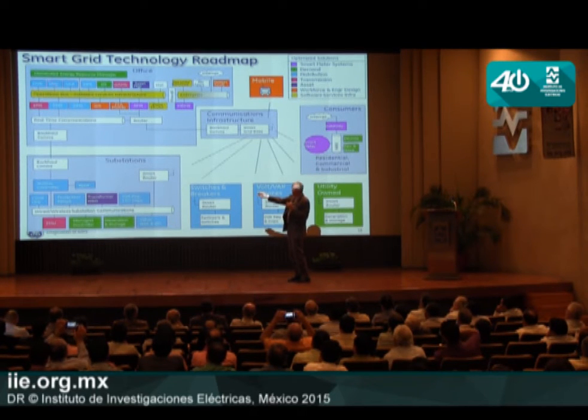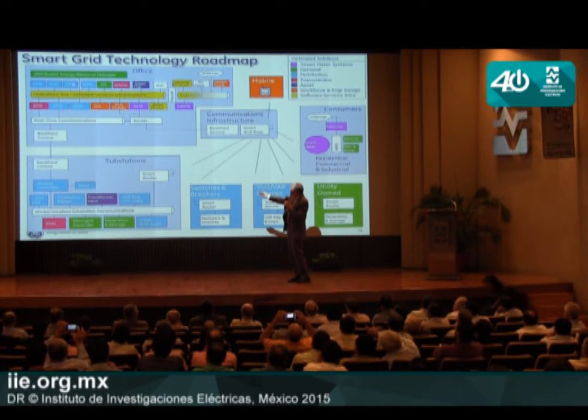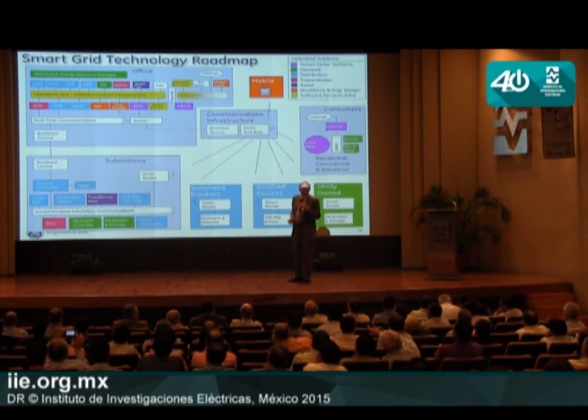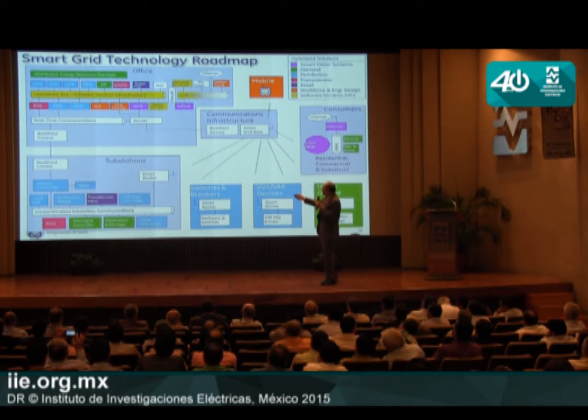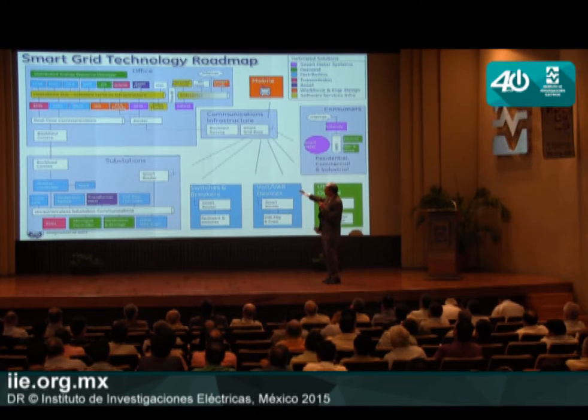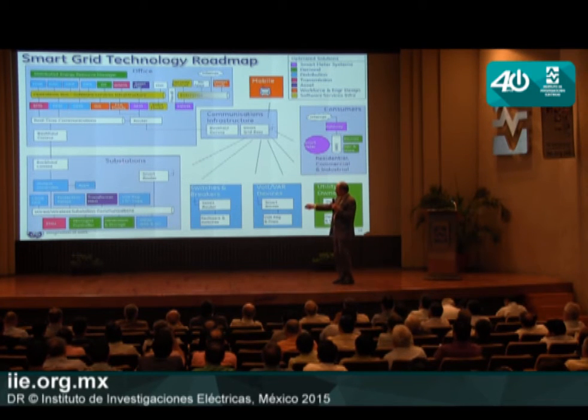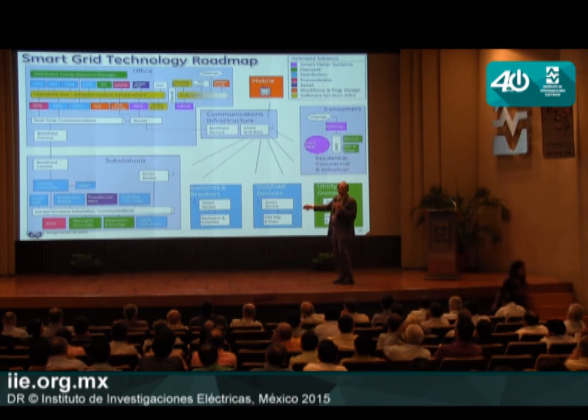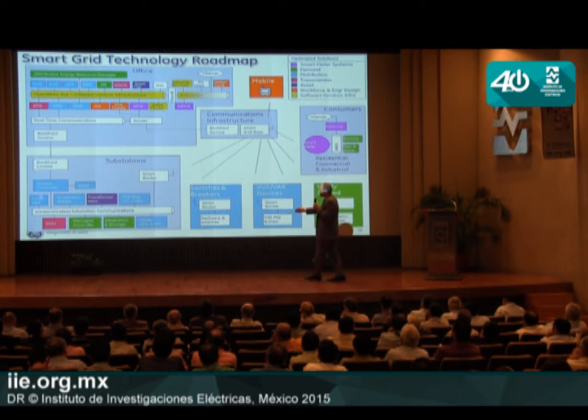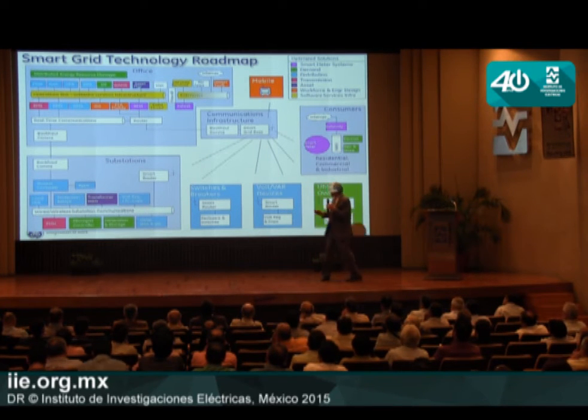So there's fault detection, isolation, restoration, integrated volt-var control, optimal feeder reconfiguration, distribution power analysis. That's our 3-phase unbalanced load flow here. These are the systems, distribution management, outage management, and these are located in the office or the control center, all right? Now we go down to the substation, and here we have our data concentrator, our station controller. And like I said, we're distributing the intelligence so we can run volt-var control and fault detection, isolation, restoration at the substation level. We have a local user interface and other microprocessor-based devices in the substation.